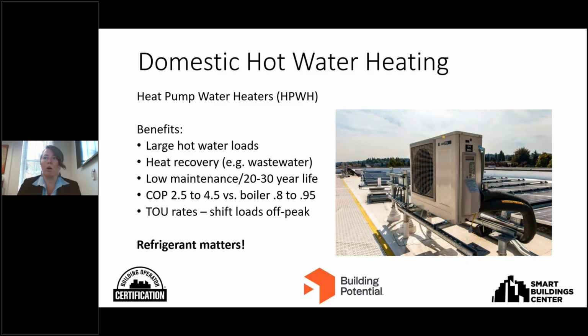It requires wastewater storage, but it can dramatically reduce the electrical load needed, up to about 50%. That's a pretty good benefit. I'll also note these are very low maintenance, they have a pretty long life, and they can be used to shift loads to off-peak because they have the ability to store heat in the form of hot water. There's a case study in Seattle doing just that.